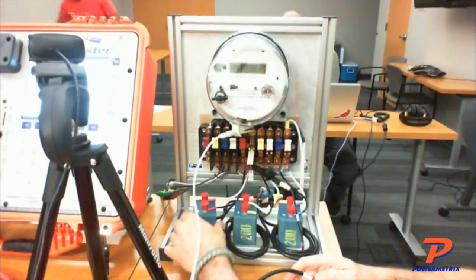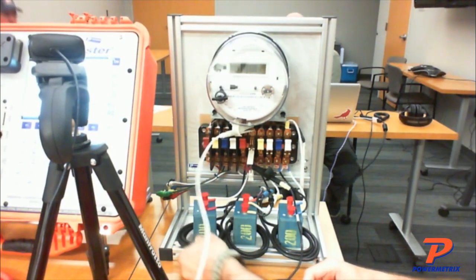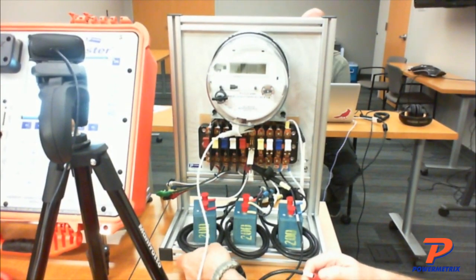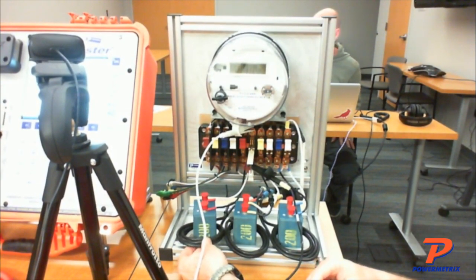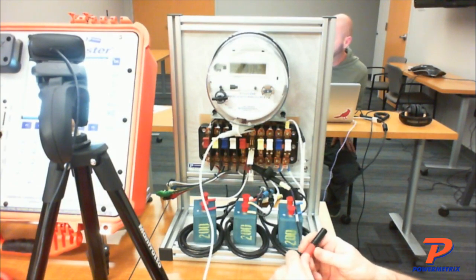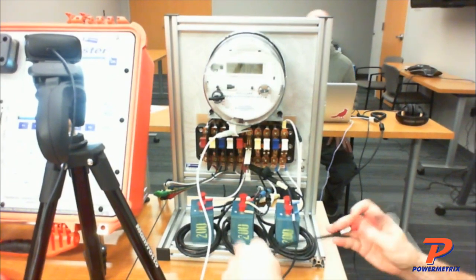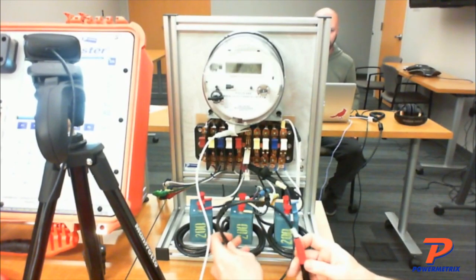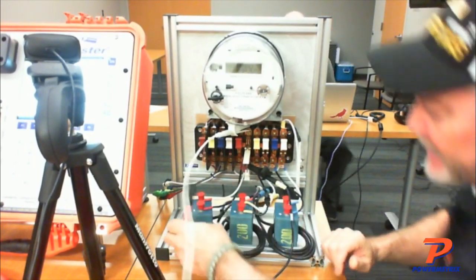Here on my A phase CT, I've got primaries that are already running through it. That would be your existing cables that would be there if you're out in the field. And I'm going to add this drive cable to it. Remember, you want the drive end to be on the dot side of the CT.